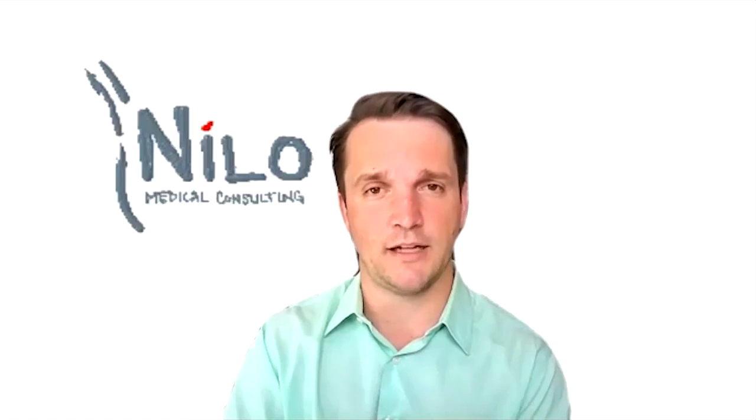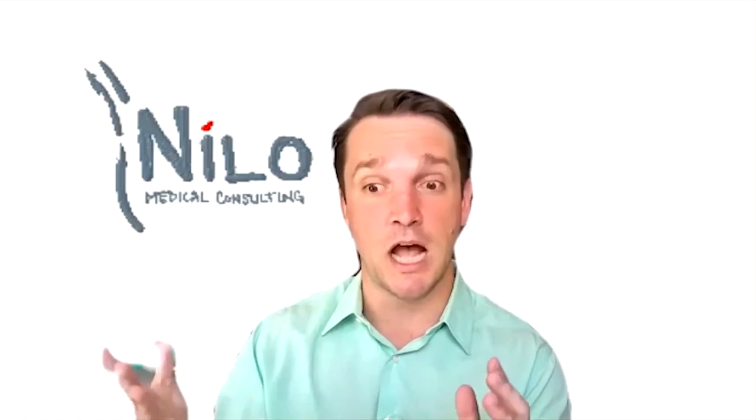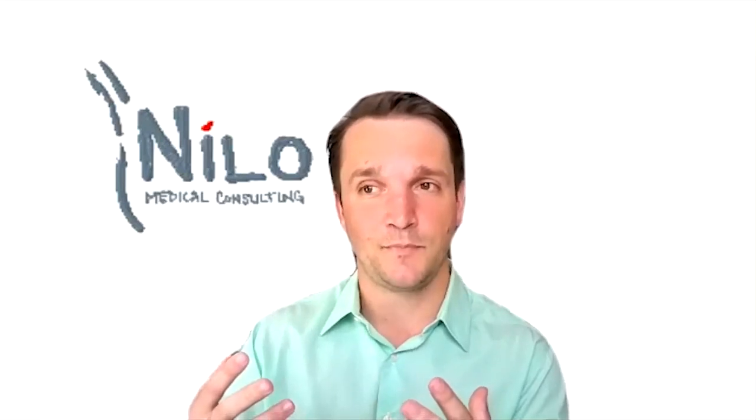The other two big things for software evidence are going to be the human factors, the usability, and I mentioned that earlier, and the cybersecurity. Most of the laws are written for a screw, like a dental implant. A typical non-software device will have mechanical testing, biocompatibility, electrical, all those sort of things. With software, there are only those three main things that they can look at to show that your device works.